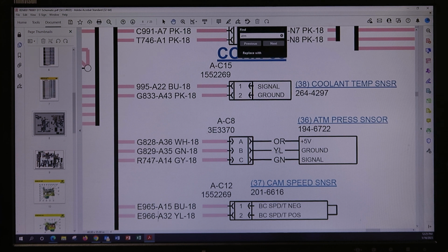We go ahead and we check the sensor, and the sensor's good. So now we're looking at the signal wire, and we've checked it here. We've crossed it, the B and C wire, and it didn't change to a -4 FMI. So we suspect we might have an open in this signal wire. So we need to know what these numbers are.